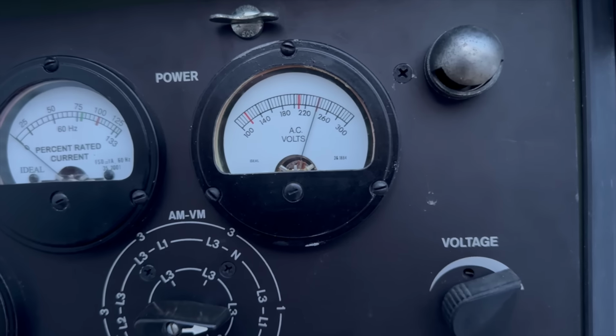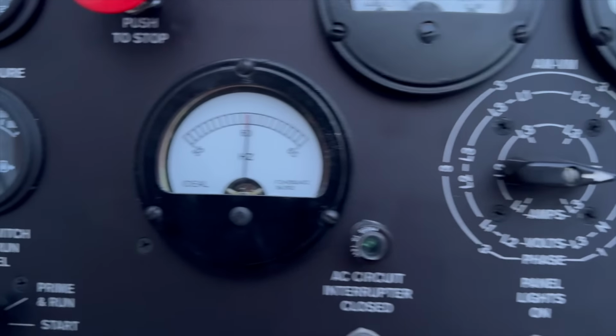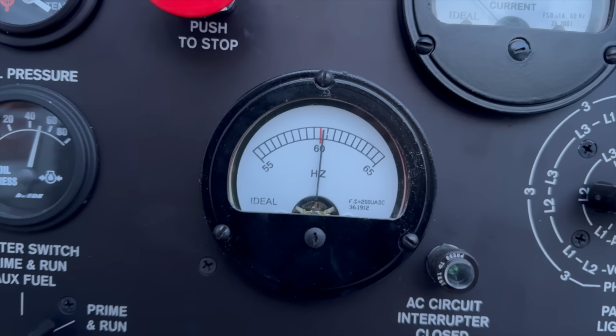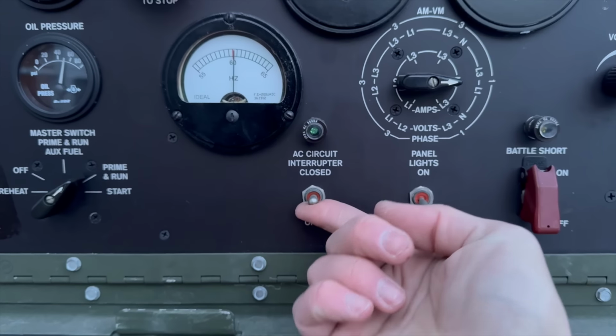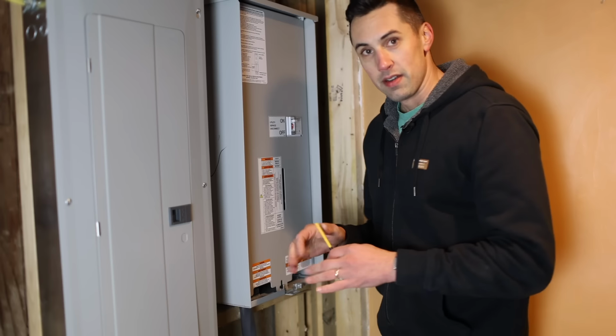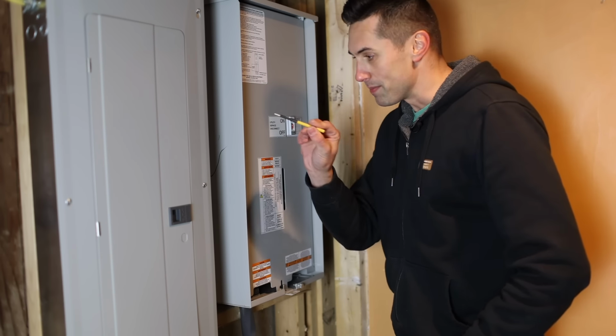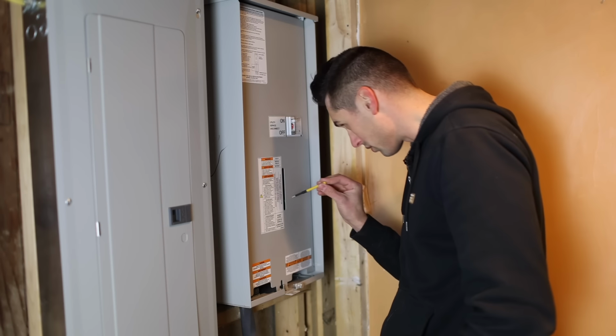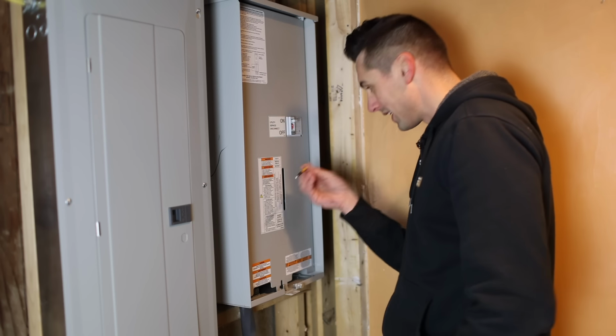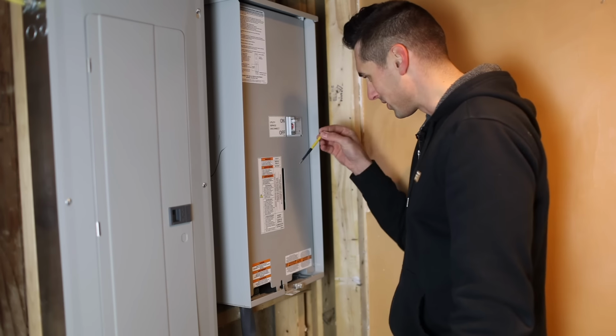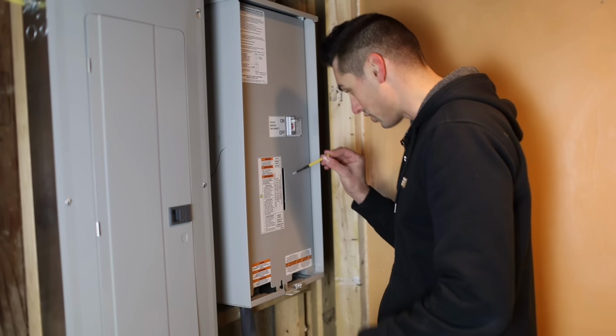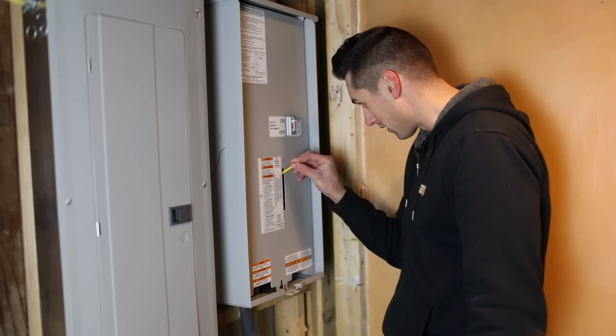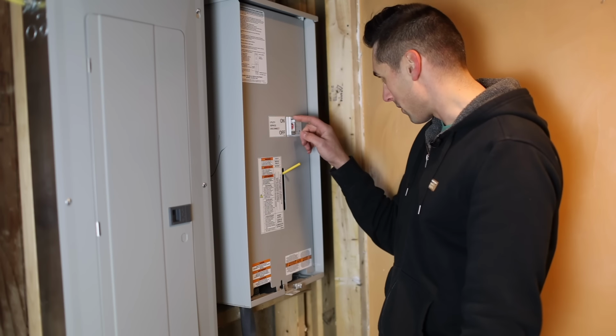Okay, so the voltage is good, 240 volts. The frequency is right about at 60 hertz. I'm going to go ahead and close the circuit interrupter. Now from the inside, they give you this little handle to manually switch it, which goes in here. It's insulated for 600 volts because I'm sticking this into an enclosure that is charged. Right there. Yeah, so shut off power to the house first.